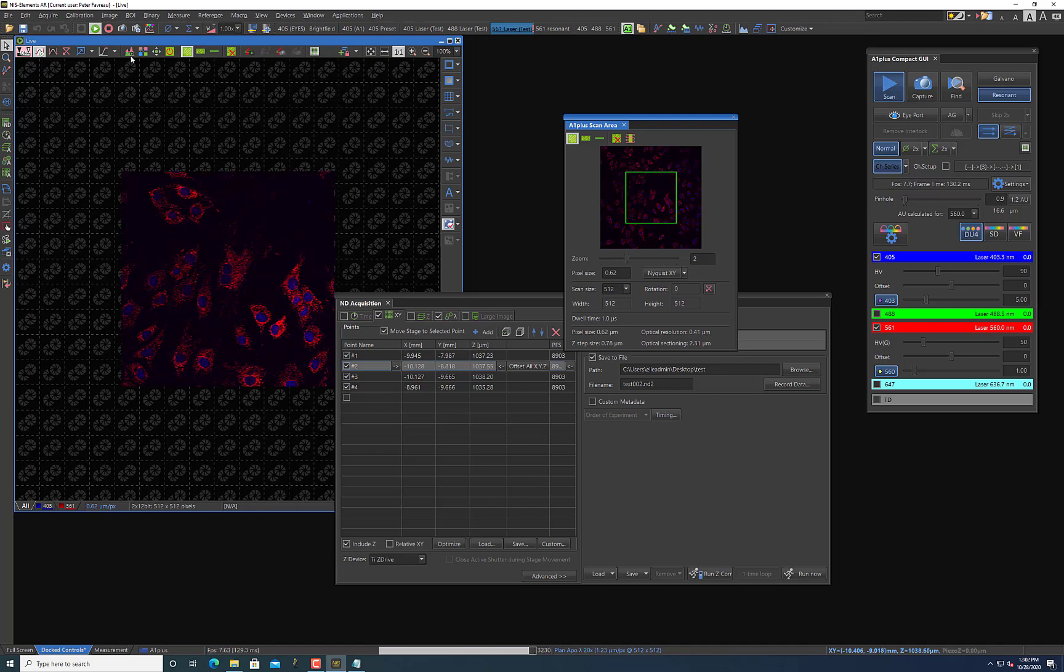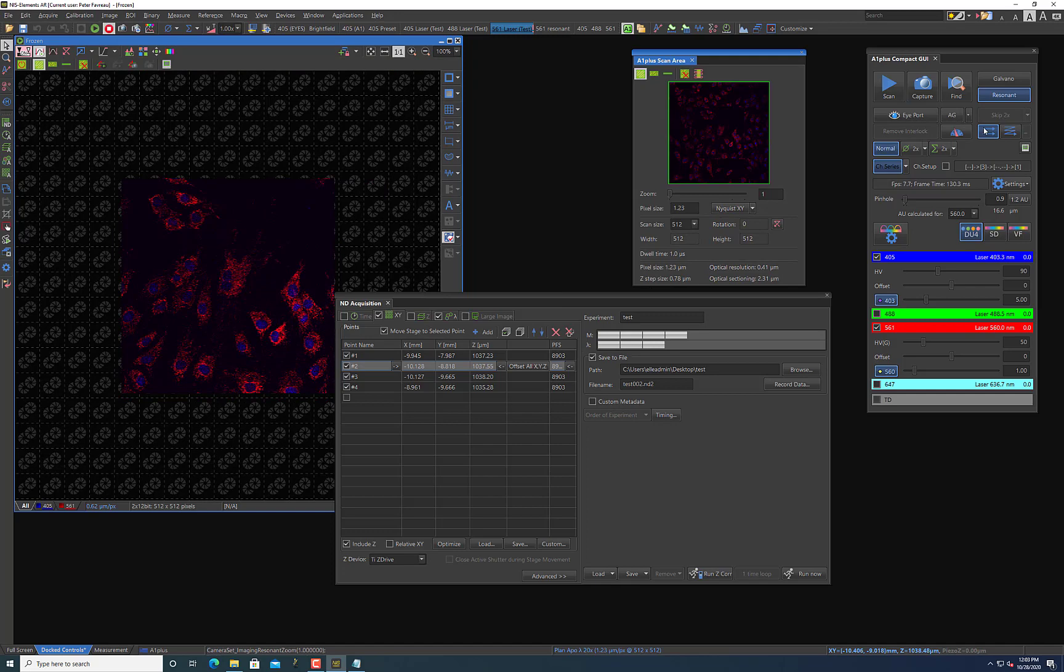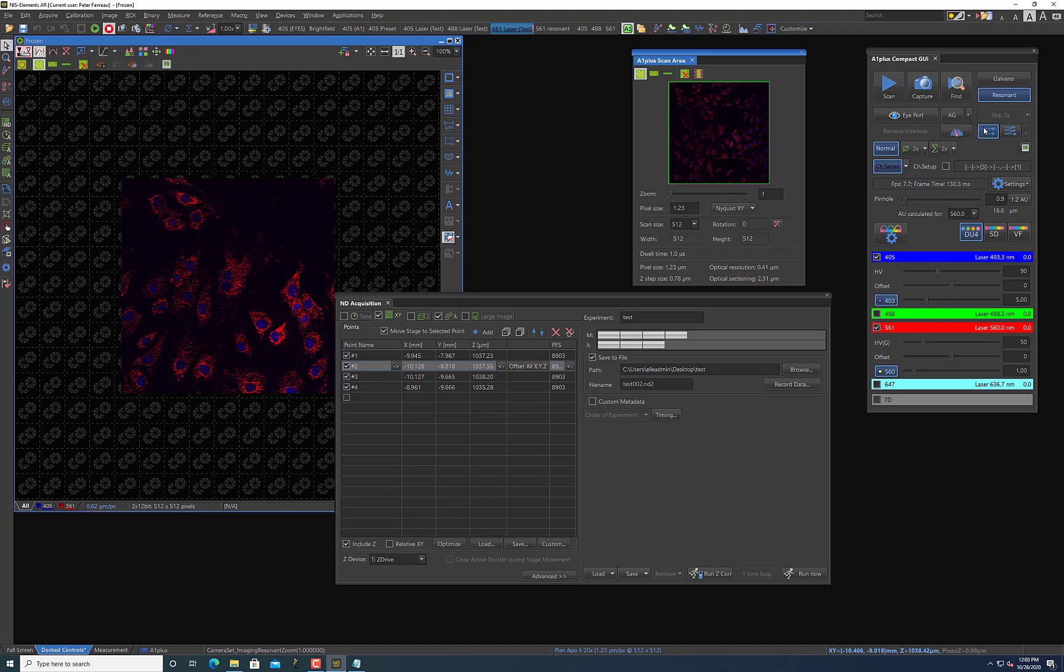And this isn't really the only use of the resonant scanner. It can actually be used for something like photo activation experiments where you can use it in tandem with a galvano—use the galvano to ablate a certain region of your sample and then use resonant mode to quickly capture those dynamic events that happen afterward. So you can capture maybe the diffusion of your fluorophore or something. So using these in tandem is also possible. I won't show that in today's video because I don't have a sample that's able to do that, but it is quite possible to do that and that's another very common use of this technology.